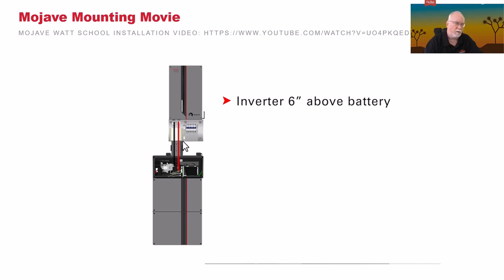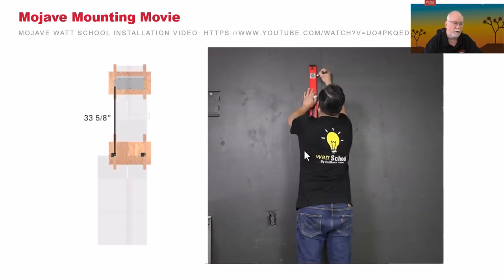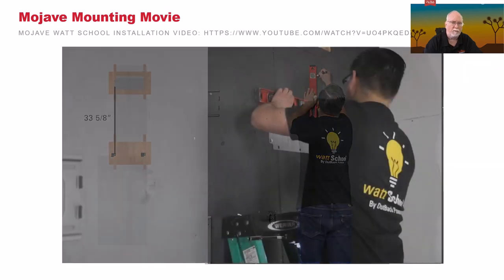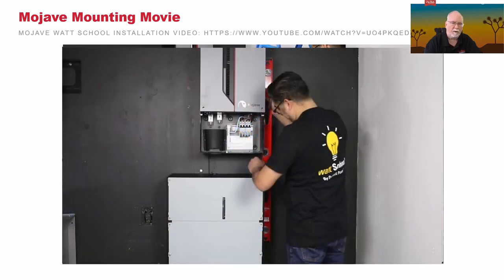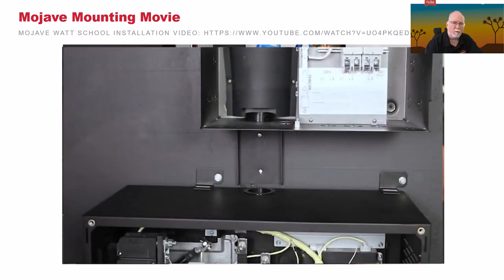This is an important step here. The inverter needs to be 6 inches above the batteries. If you make it 7 inches, these are going to be too short. If you make it 5, you're not going to be able to get this in there. So you need to make sure that you have 6 inches between the 2 units. He'll show you where to measure this up. Another alternative method is to measure 33 and 5/8 inches above that. Again, he uses a level, puts the unit up on the slide, slides the battery in underneath it. I would suggest you do it in that order, because it's very hard to reach over the battery to try to hang the unit. Here he's bringing it in, making it level on the 2 sides, and then he's putting in those last securing bolts that we talked about. One item I left off is to put in this chase. The only thing I'll tell you on this is make sure you protect the top of the battery. You don't want these screws dropping into your ESS compartment.